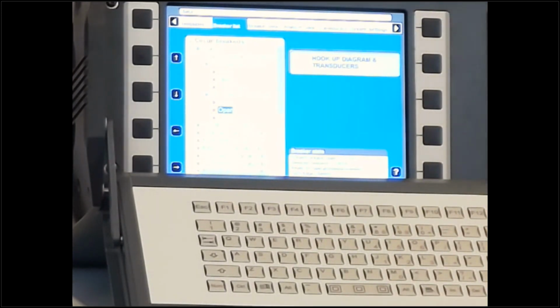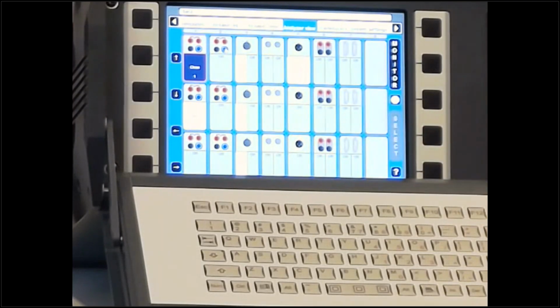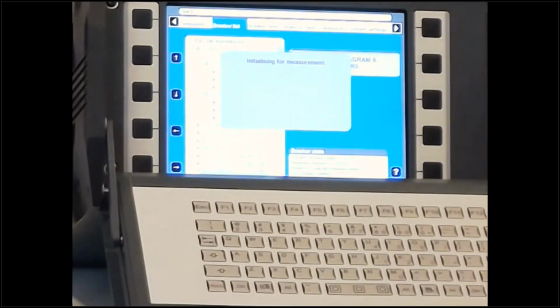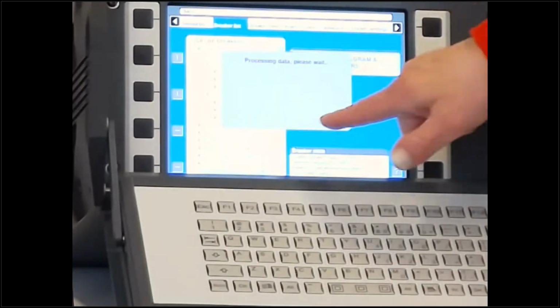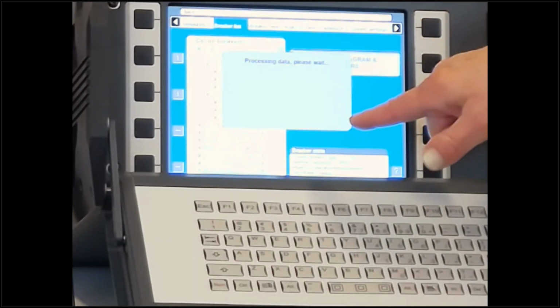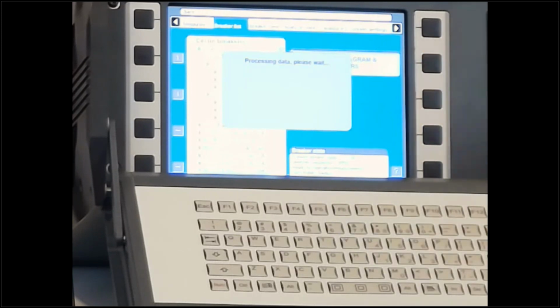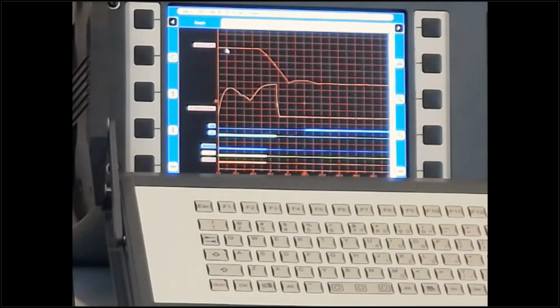After this, you shouldn't move the cables. They are now tuned to this position. And I can do the open operation. So I'm going to start measuring by turning the knob. And that's going to be a bang. You notice it has a bar here before it starts. So if you, for some reason, don't want to be close to the circuit breaker when you operate it, you can set that timing to a longer time, like 120 seconds or something, right?